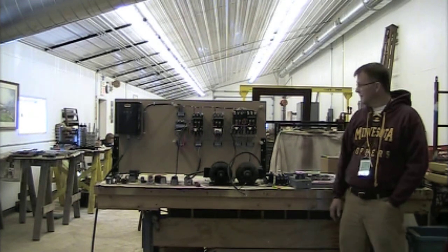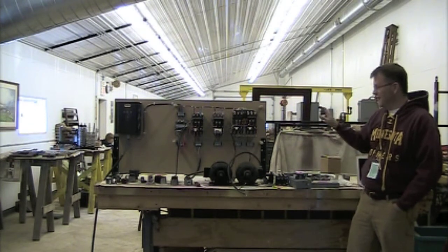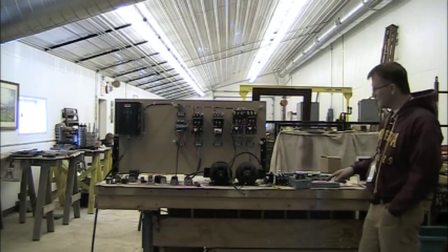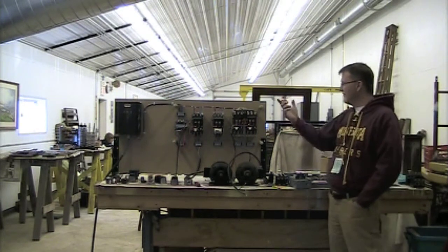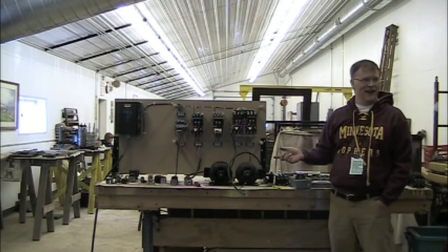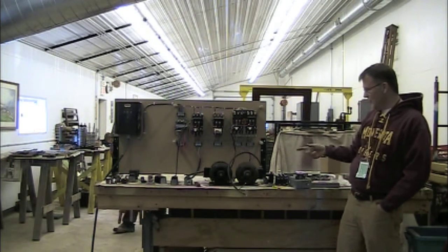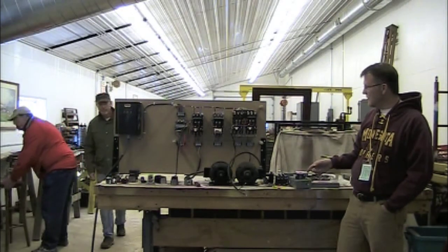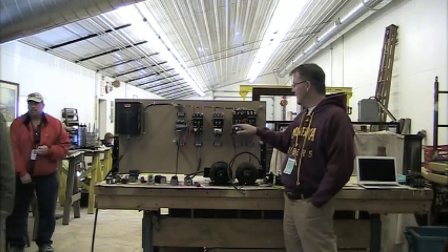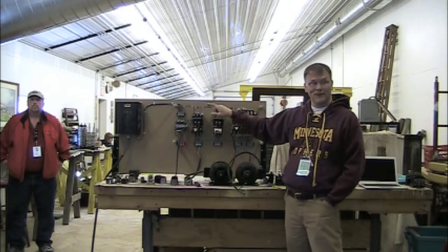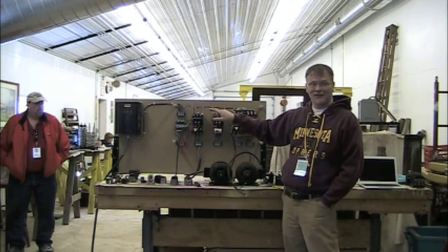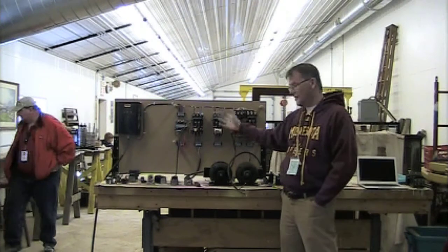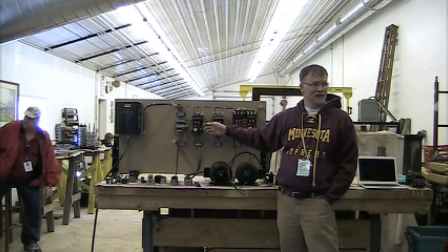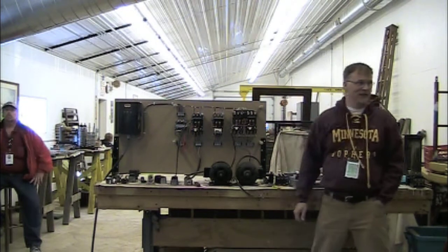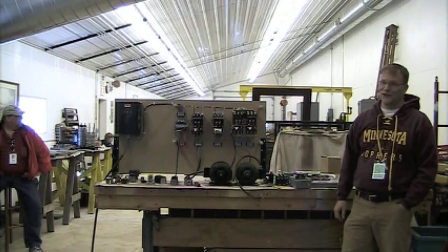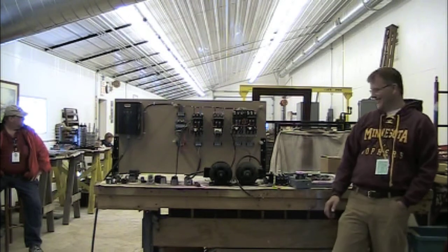Yeah. And I even had a good example here this morning. I plugged in the extension cord that I brought, and all of a sudden the motor wouldn't start with single phase, because I didn't have continuity through one of the leads on that extension cord. But since it was coming off the control transformer, I had power through the 2 leads that I did have power on, and it tripped the overloads on the starter because the motor was sitting here trying to start single phase and kicked off. Did exactly what it was supposed to. It would have been a good part of the demo. I'm glad that didn't happen.